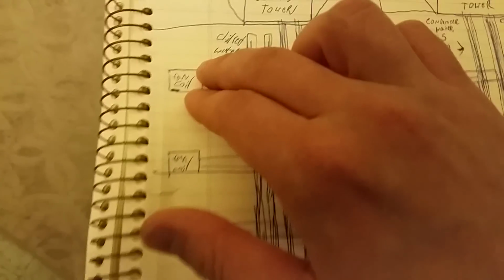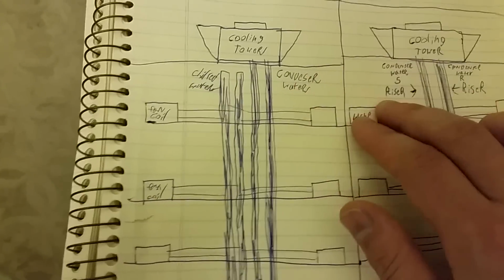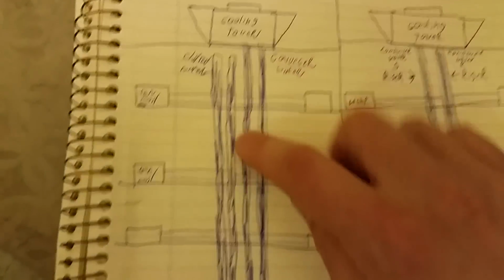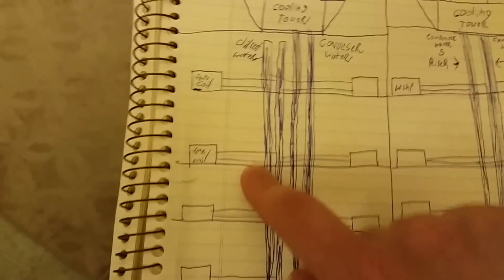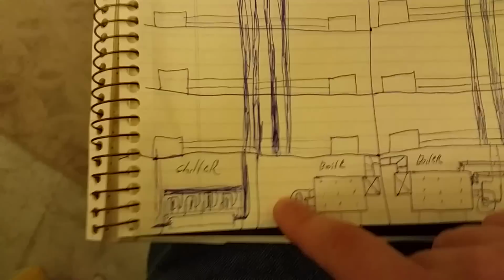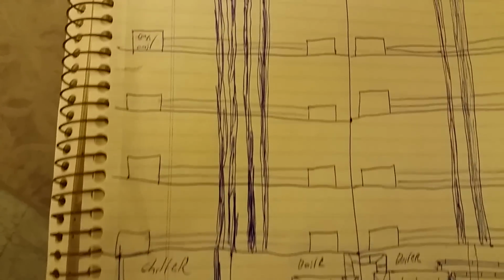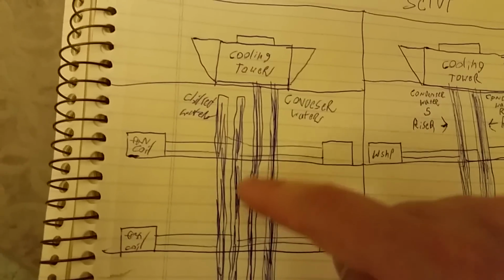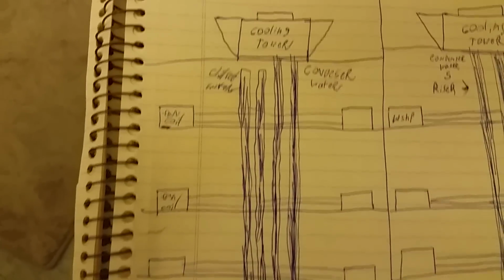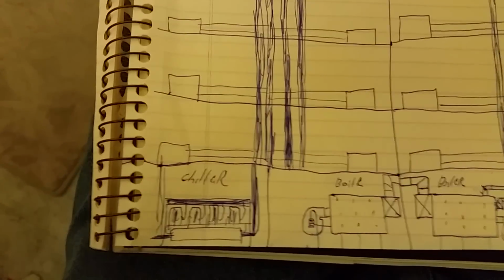In a 4-pipe system, there's another set of risers, so you have 2 coils in each fan unit. You have a chilled water coil and a hot water coil. And that's why they call it a 4-pipe system. Supply and return for the hot water, supply and return for the chilled water. Again, obviously, I didn't draw pumps, I didn't draw strainers, but each of these units usually have strainers, backflow preventers, all that good stuff. Sorry for the shaking there. So, chilled water comes up, feeds each fan coil, goes back down to be recooled by the chiller. Usually, a lot of these buildings keep their water 52 degrees, 50 degrees, depending on the outside temperature.